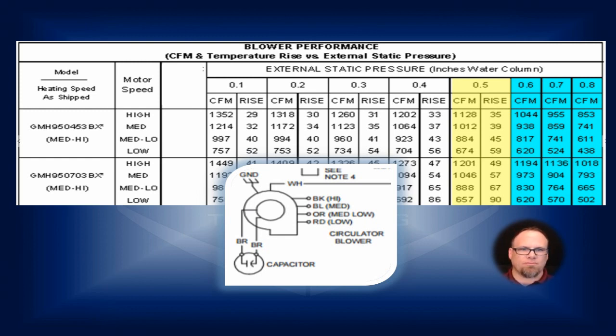You add the raw numbers together. Okay, now for those of you mathematicians, that might be a bit of a tough stretch, right? You stick it before the blower, it's sucking, so it's a negative pressure. You stick it in after the blower, it's blowing, so it's a positive pressure. We don't care about the negative and positive. You take the negative and positive, you crinkle it all up, and throw it in the floor because we're adding raw numbers. So in this instance, if you measured your static pressure and it was negative 0.4 before the blower and positive 0.4 after the blower, those don't equal zero in this particular example. They equal 0.8. And if you look at our example here on this GMH95, if we had 0.8 inches of static and we were on high speed with this air conditioning system, we'd have 853 CFM.